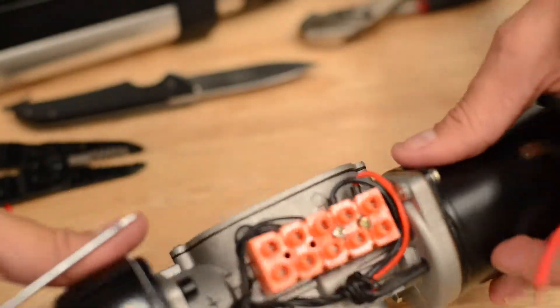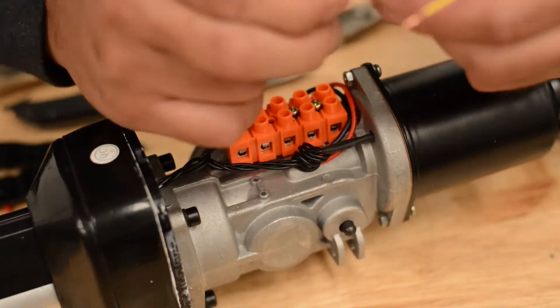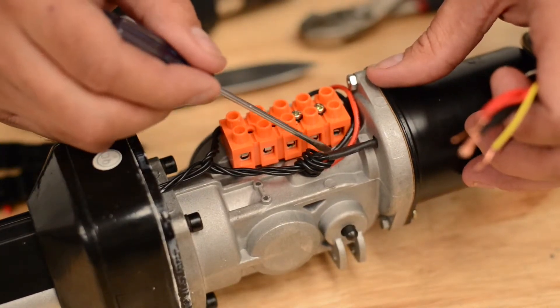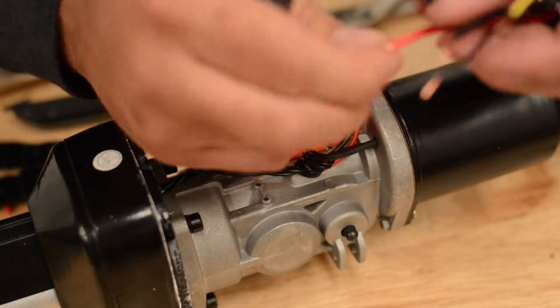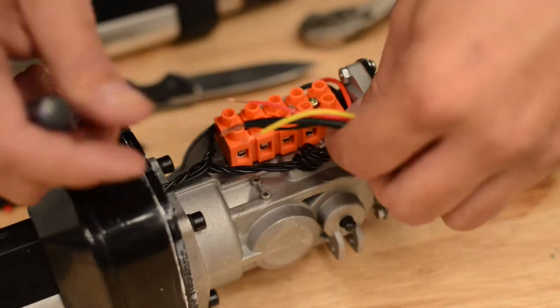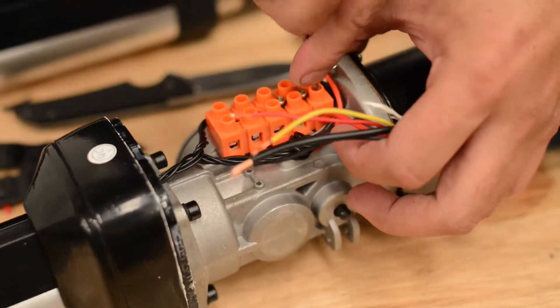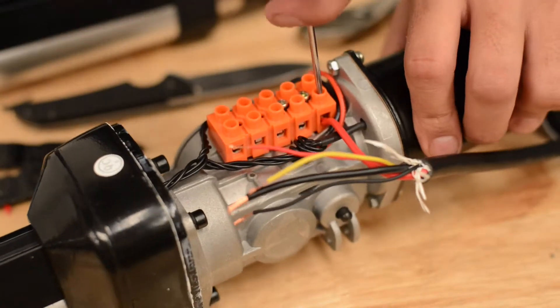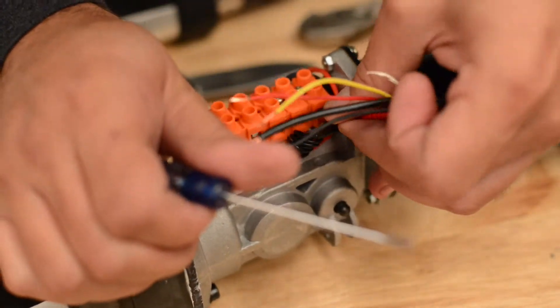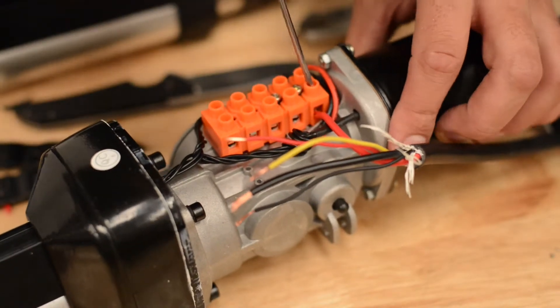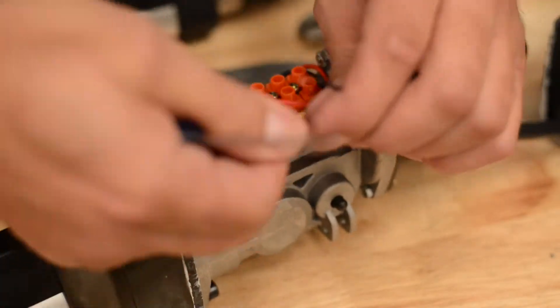And then we're simply going to put the wires back into where they were. As I said before, the larger wires are color coded, so you see red then black. One thing you want to avoid here is you don't want the bare wire touching this housing, so you want to make sure you cut this wire short enough so it can go all the way in there. You see now there's not really any exposed wire there to touch anything. Tighten this down as best you can and give a little tug on the wire to make sure it's in there correctly, seated in there correctly. Make sure you have a metal to metal connection. It's real easy to tighten it down, and if it's not making a metal connection, it's not going to obviously work.